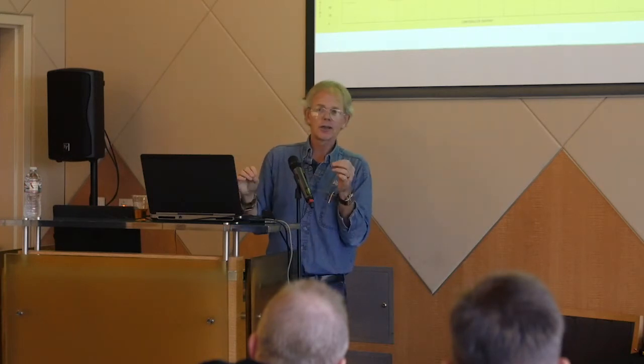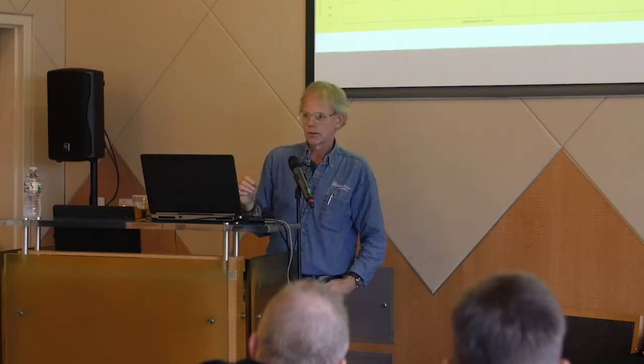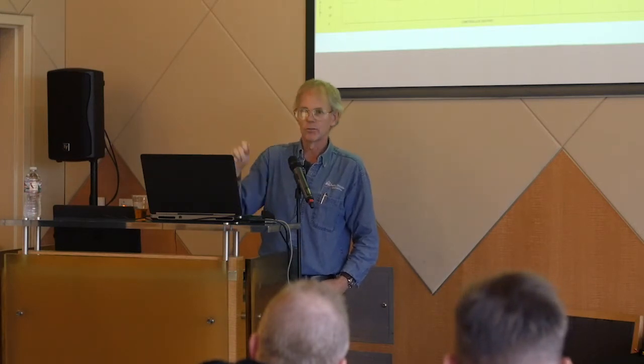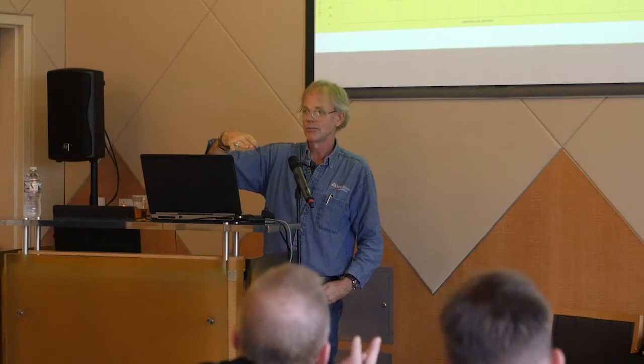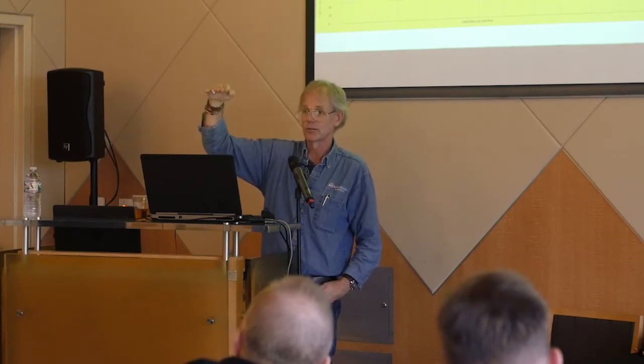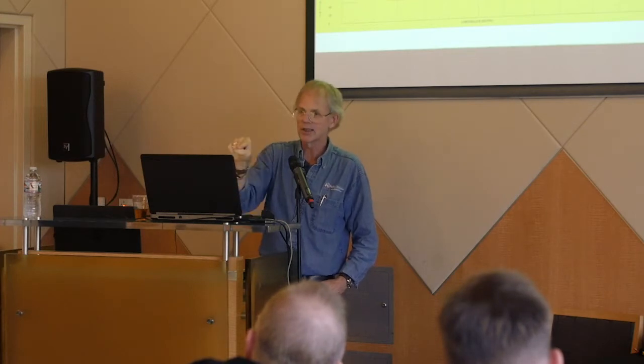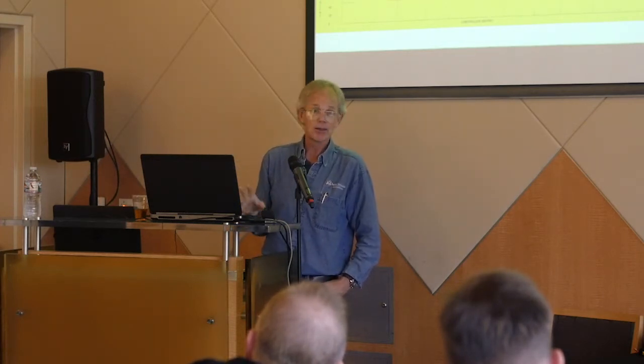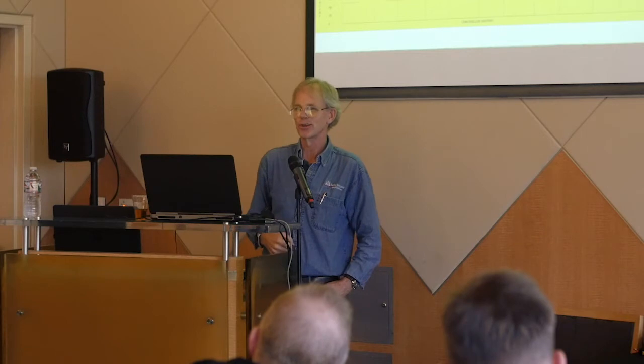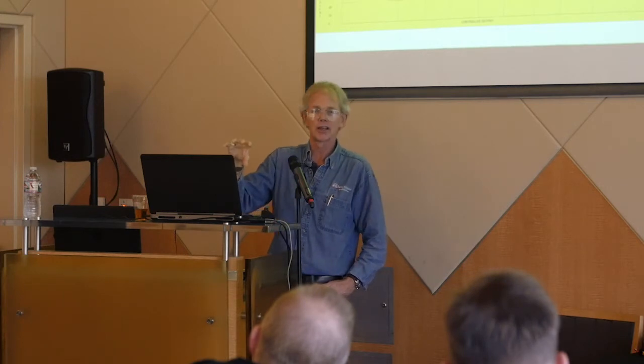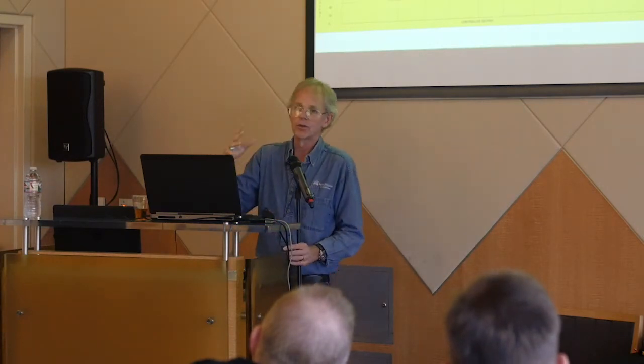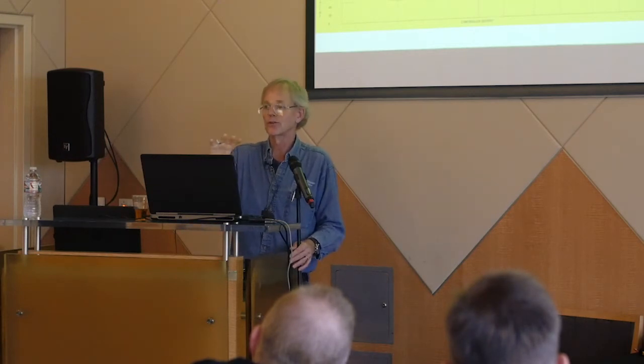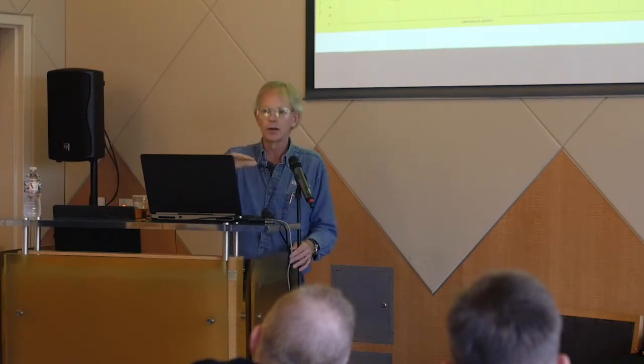Okay. Another thing you have to watch with auto-tune, at least some of the older ones, one way to do tuning is that open loop test. You basically take the system, put it in manual, get it as stable as you can, and then put a step change in. There are controllers out there that when you hit the auto-tune button would do just that. And that may not be a very good thing with the duct static pressure control process, for instance. I'm going to jack the set point up 3 inches and watch what happens. Well, the duct's going to break for one thing. So you really want to understand how that auto-tune process works before you implement it. So some of that's personal opinion, but I can tell you there are a number of different algorithms. That's why the parameters are different from manufacturer to manufacturer.